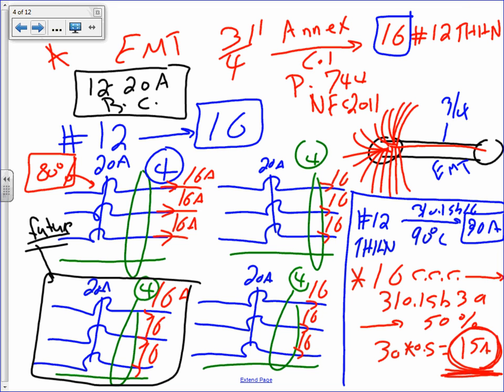Now let's see about the rating. So conduit fill, yep, I'm 16 conductors, I'm 16, right? Conduit fill, okay. How about grouping, the rating, right? If you do the rating, you end up with 15. So if you group them all together, you only lost 1 amp. So the only thing I do, just to give you an idea, is always group your circuits. Can you give a thumbs up, Chad?